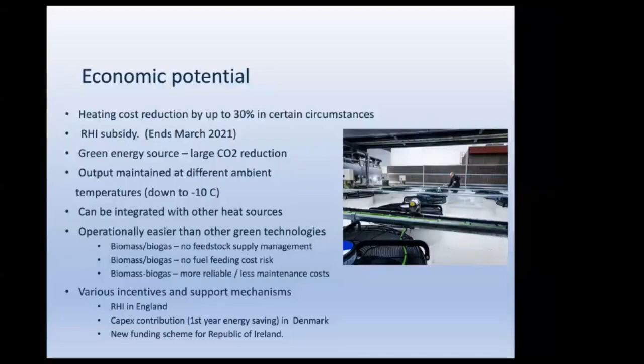I think the line there that I'd like to talk about is the integration with other heat sources. I think that if a commercial building especially has got a fully functioning fossil fuel system in, then rather than contemplate taking it out, a really good alternative is a bivalent system. Put a heat pump in, allow it to do up to 90% of the load, can reduce the carbon footprint by 90%, but that's probably at half the price of ripping out the gas and going for 100% heat pump solution.